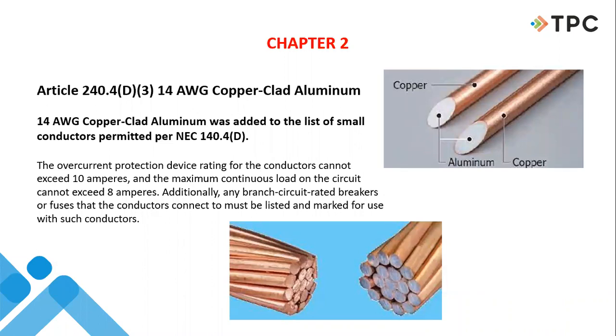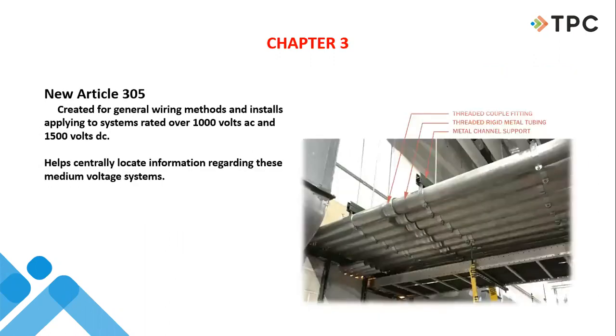Some new criteria in here for 14 gauge copper clad aluminum. With the cost of wire, I think everyone could see this coming. There's going to be a new welcoming of copper clad to the industry. Overcurrent protection device rating for the conductors can't exceed 10 amps for the so-called 14 gauge copper clad, but they're making room for it in the industry.